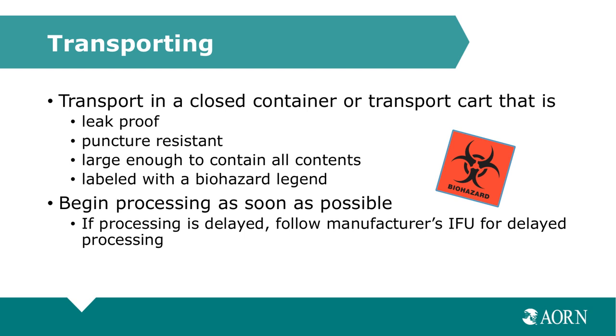And that cart or container must be leak-proof, puncture-resistant, and large enough to contain all of the contents, and it must also be labeled with a biohazard legend. Now, your processing should begin as soon as possible after the device has been transported to the endoscopy processing room within the manufacturer's recommended time to processing. And when it's not possible to initiate that cleaning process within the endoscope manufacturer's recommended time to cleaning, then the manufacturer's instructions for use for delayed processing should be followed.